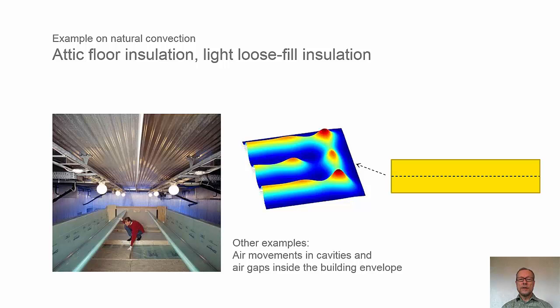In Swedish cases, we could have up to 700 millimeters of insulation on the attic floor. What can happen is that in some parts, the warm air from the bottom surface starts flowing up. We get a plume of warm air flowing up. In the same way, this will be exchanged with cold air flowing downwards. We have the blue zones.